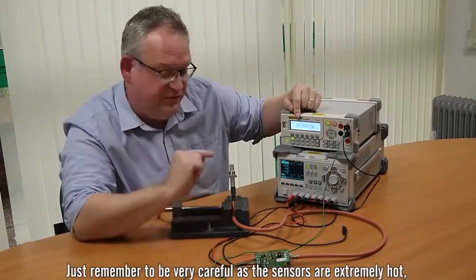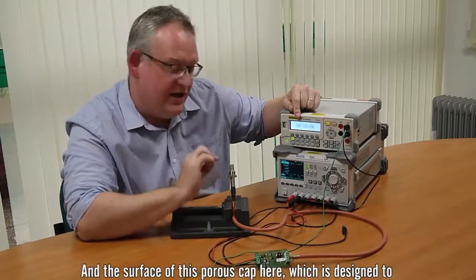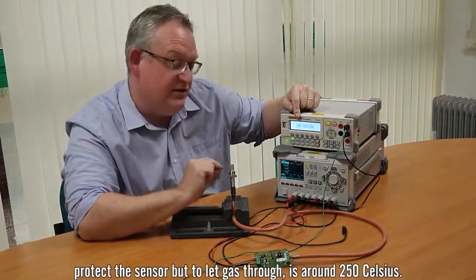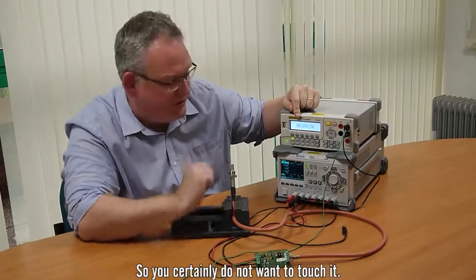Just remember to be very careful the sensors are extremely hot. They're heated to 700 celsius inside and the surface of this porous cap here which is designed to protect the sensor but to let gas through is around 250 celsius so you certainly don't want to touch it.